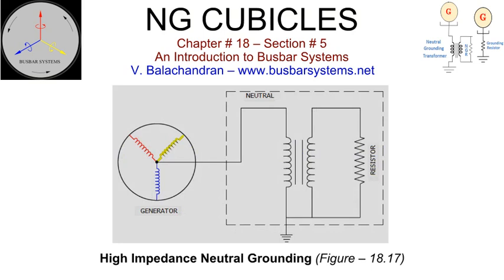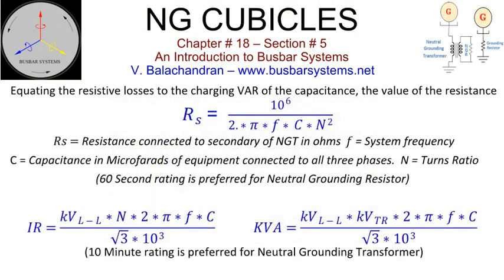High impedance grounding is recommended for large-sized generators. For large-sized generators, it is the practice to connect its neutral to the neutral grounding transformer loaded with a neutral grounding resistor. When the effective neutral grounding resistance value is high, the generator may experience high transient overvoltage due to switching operations of the breaker or arcing faults to ground. The magnitude of the overvoltage is dependent upon the value of the grounding resistor and the capacitance to ground of the generator connections. The higher the value of the resistance, the greater will be the magnitude of the transient voltage.